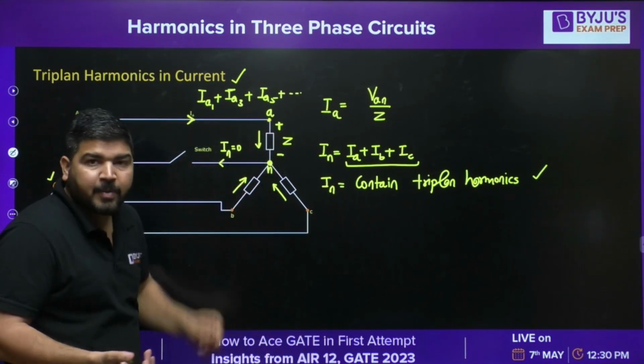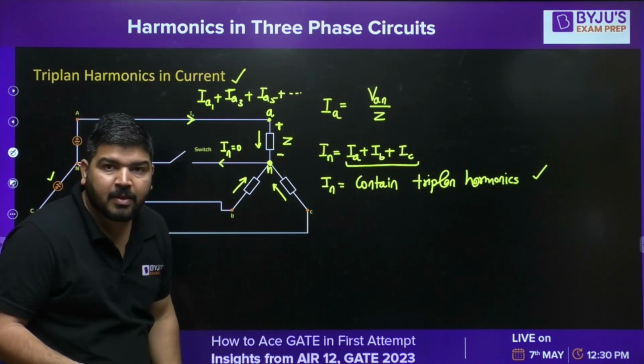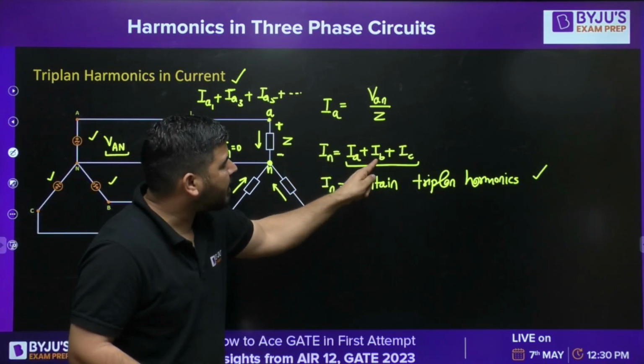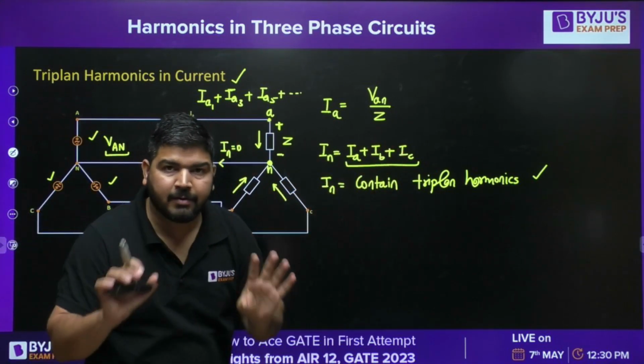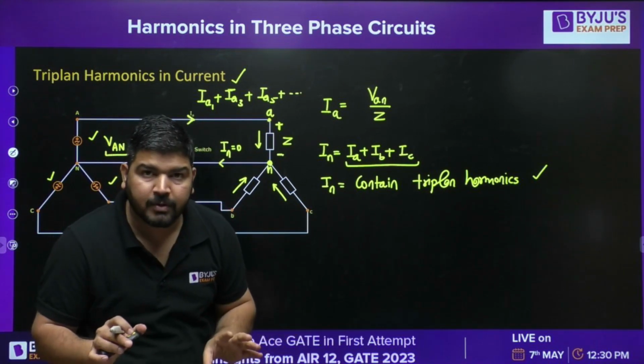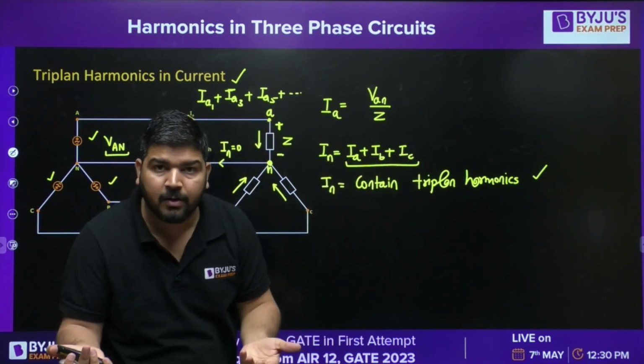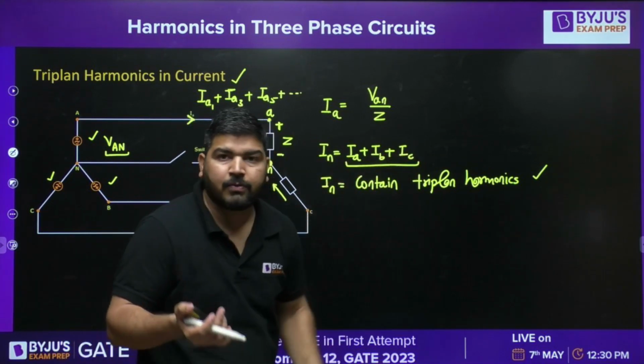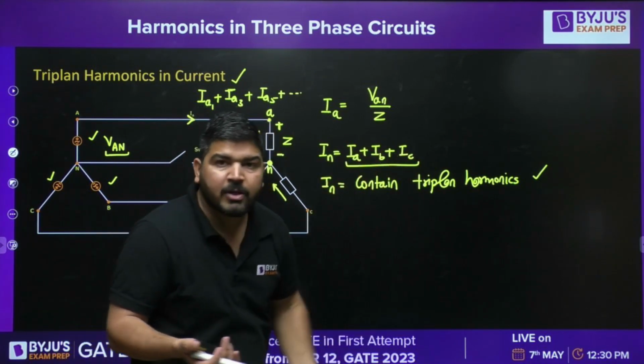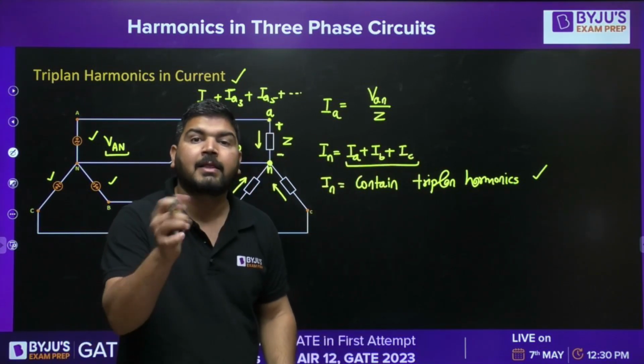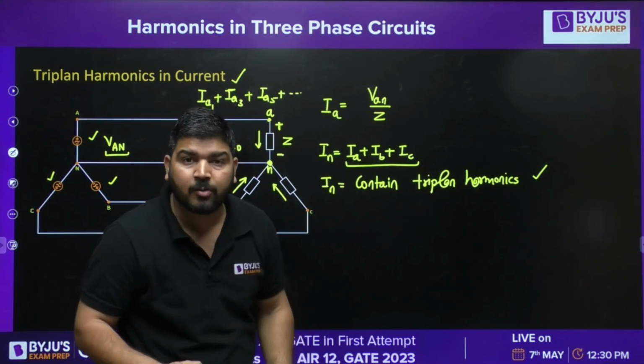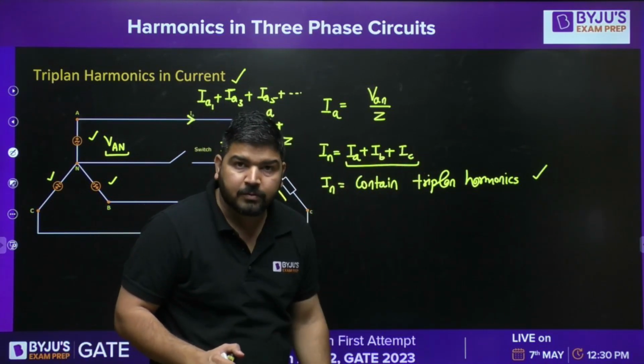But since the switch is open, the total current has to be zero. The fundamentals of these currents will be added and they will be zero, because they are at 120 degrees away from one another. So fundamental sum is zero, fifth harmonic sum is zero, seventh harmonic sum is zero. But ninth harmonic, third harmonic, 15th harmonic, that sum will not be zero.